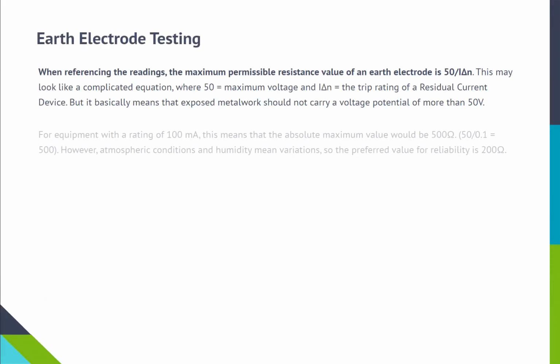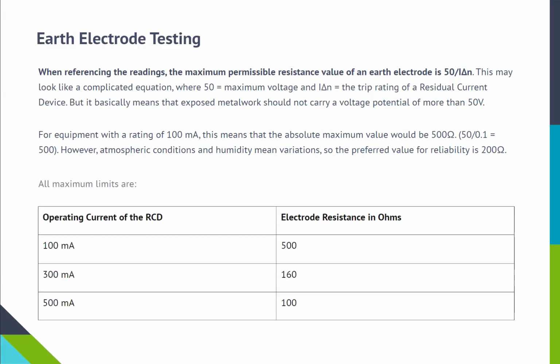When referencing the readings, the maximum permissible resistance value of an earth electrode is 50 by I delta N. This may look like a complicated equation, where 50 equals maximum voltage and I delta N equals the trip rating of a residual current device. But it basically means that exposed metalwork should not carry a voltage potential of more than 50 volts.